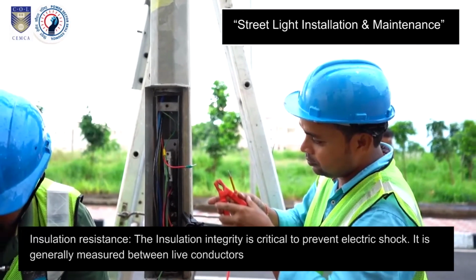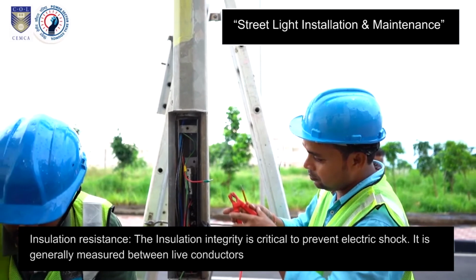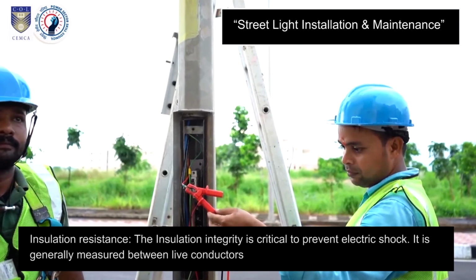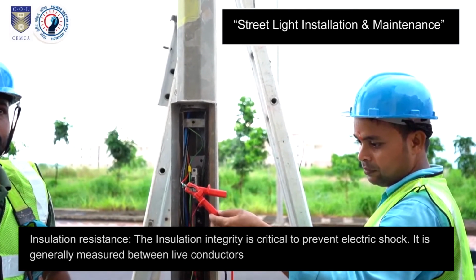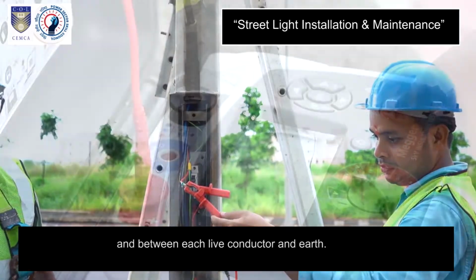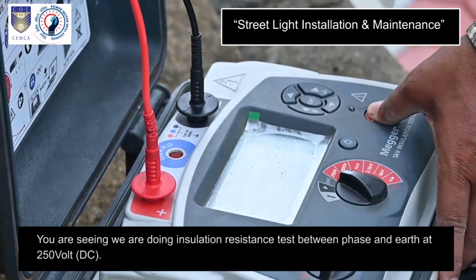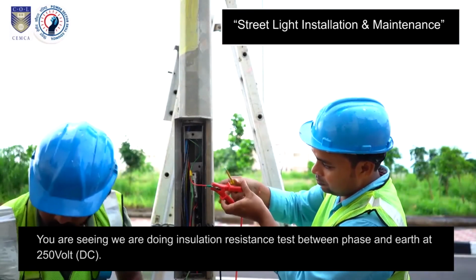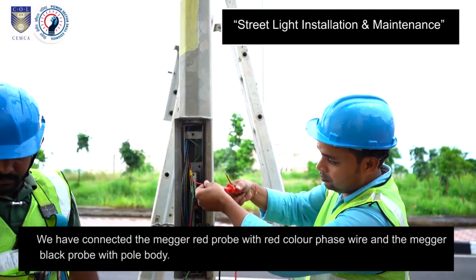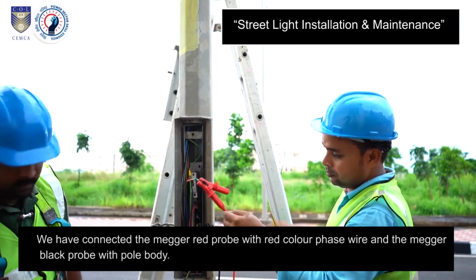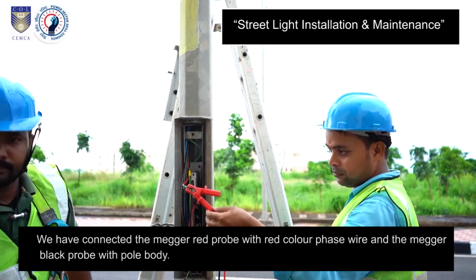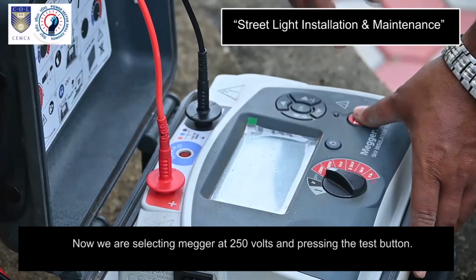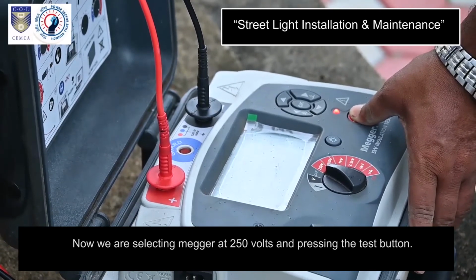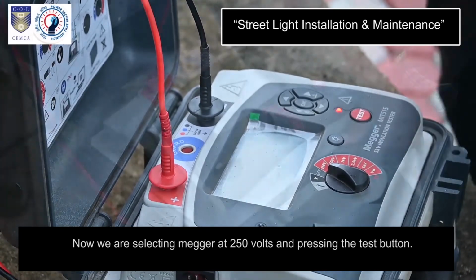Insulation resistance. The insulation integrity is critical to prevent electric shock. It is generally measured between live conductors and between each live conductor and earth. You are seeing we are doing the insulation resistance test between phase and earth at 250 volt DC. We have connected the Megger red probe with the red color phase wire and the Megger black probe with the pole body. Now we are selecting Megger at 250 volts and pressing the test button. Value coming around 5 gigaohm.